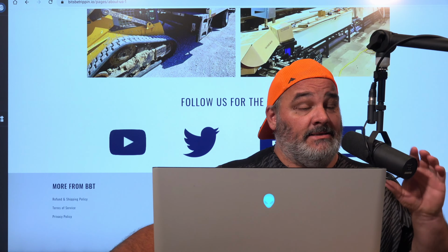So you start adding these numbers up. We're having to get a general contractor to go in there and lay everything down, buy the spools of copper to be able to hook up the services to the 800 amp panels. And there's 3 800 amp panels per container. So that's 12 service hookups with 3 lines on 3 phase, right? So you have 3 parallel 500 MCM copper lines coming through that. And then it's a math problem on the distance and timing, right?